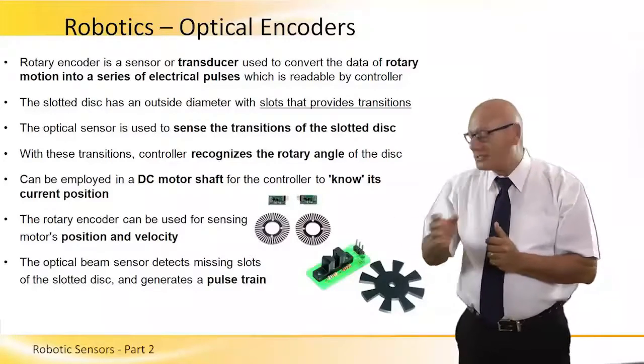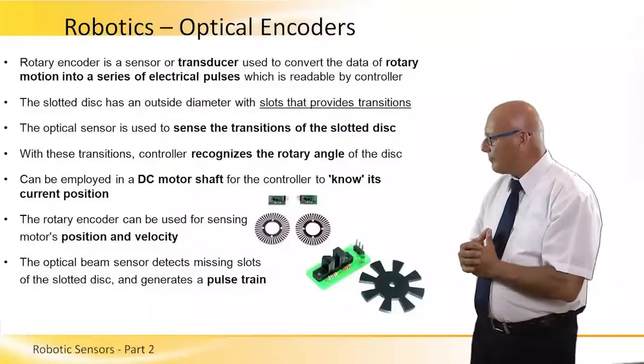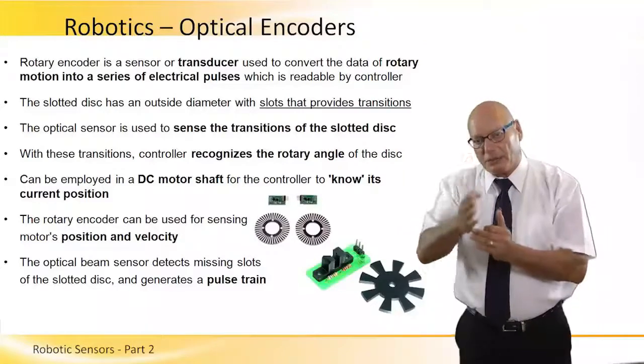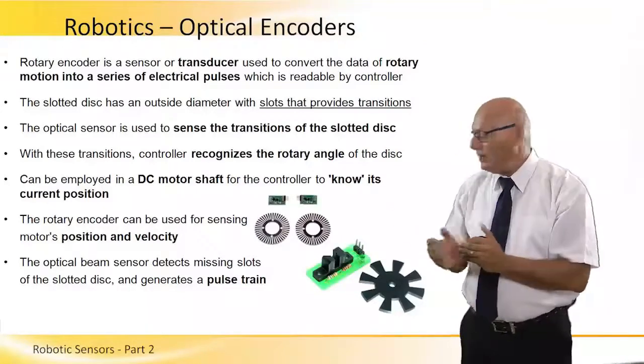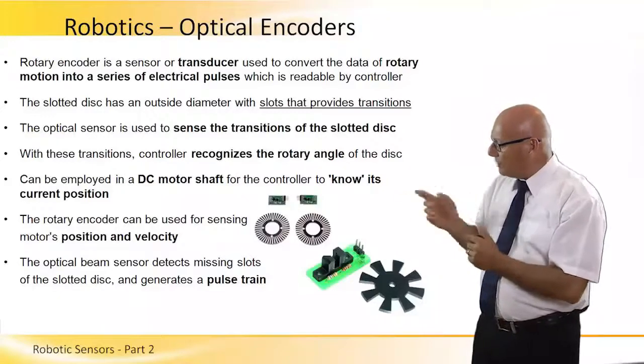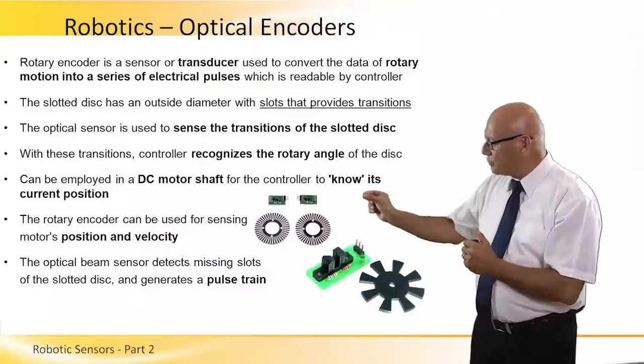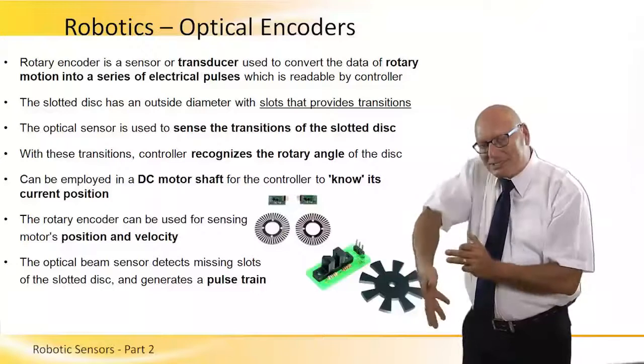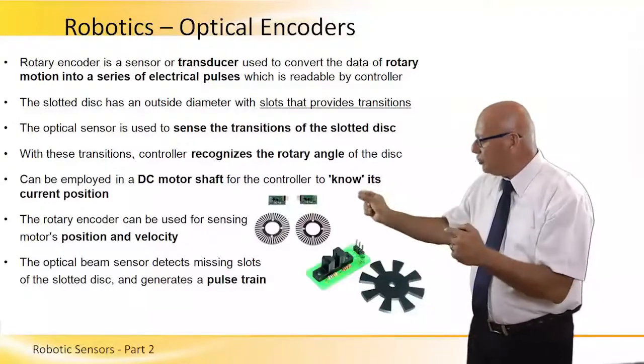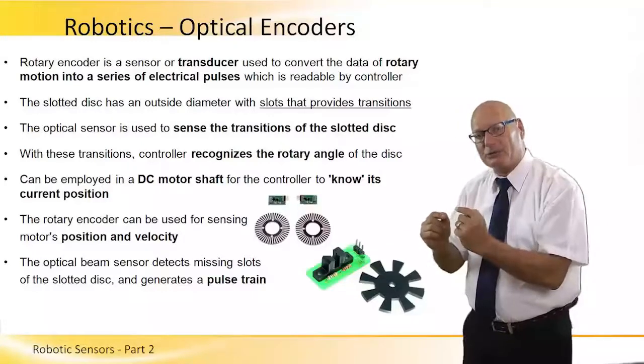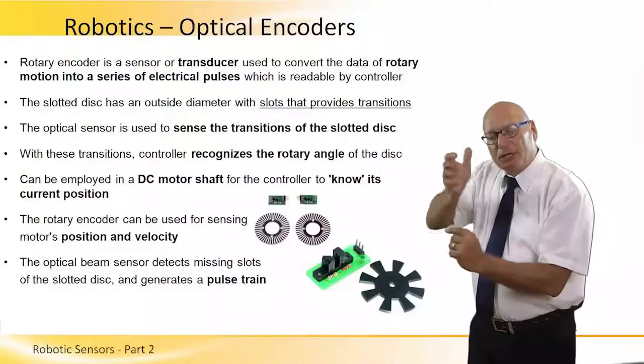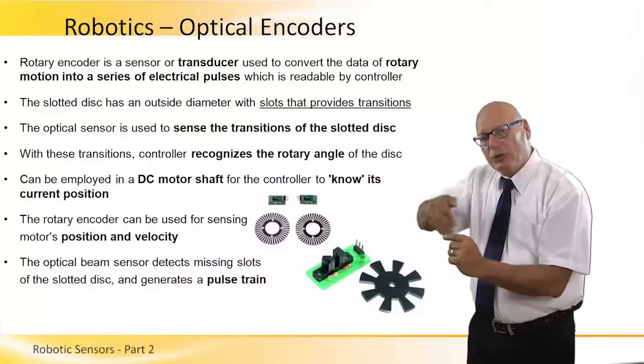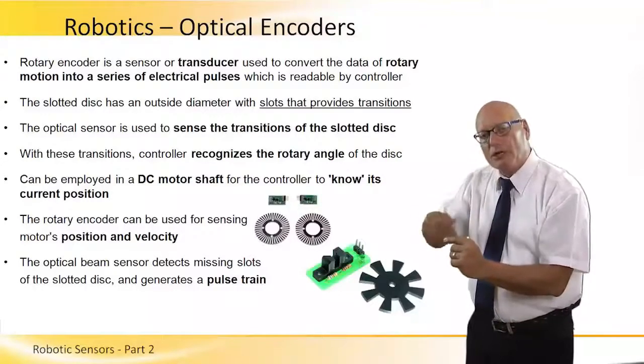The slotted disk — let's look at the disk on the bottom right. It's basically a slotted disk: black and white, black and white, alternating black and air gaps. If this slotted disk rotates in between the printed circuit boards with components on it, one side is a transmitter and the other is a receiver. As the rotating slotted disk turns between them, it will cut the beam or not cut the beam — block it or not block it. That's counting pulses.